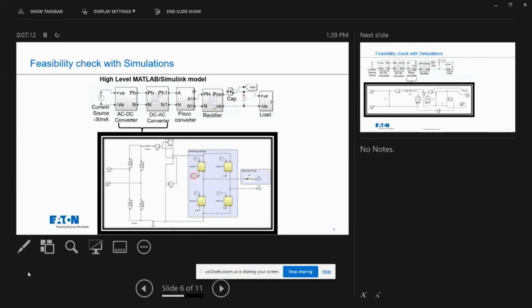As Yogesh explained the block diagram and the concept, now we would like to see how this concept will work, whether it will be able to generate the required current and voltage within the stipulated 300 milliseconds, and what the size of the capacitor should be, whether it can hold the voltage within at least 10% of plus or minus 48 volts when 20 amps is drawn from the load by the electromechanical actuator, and what the piezo transformer amplification could be. So to check all this, we used MATLAB Simulink as a platform to simulate the concept.